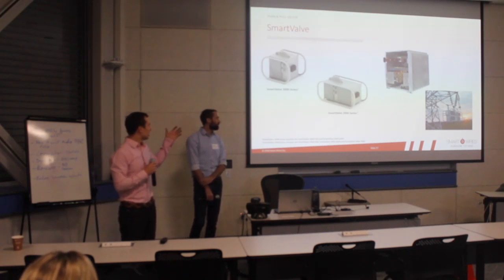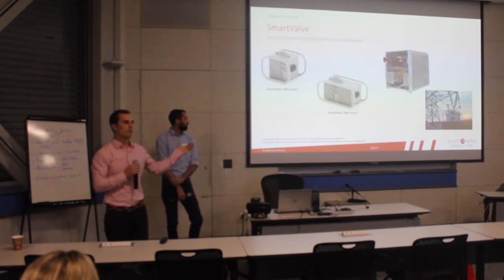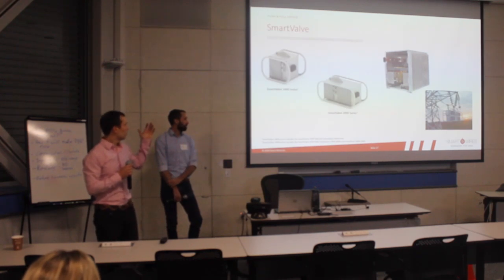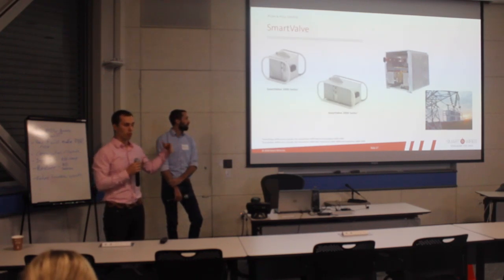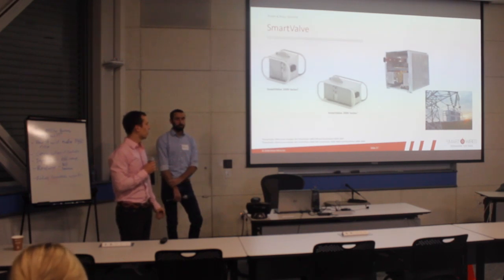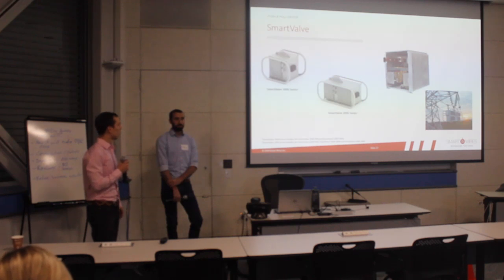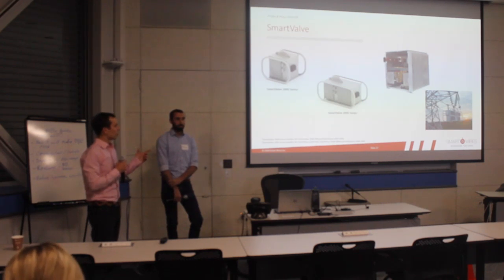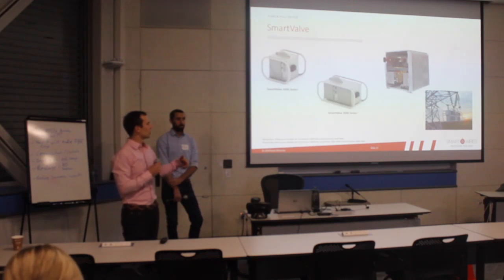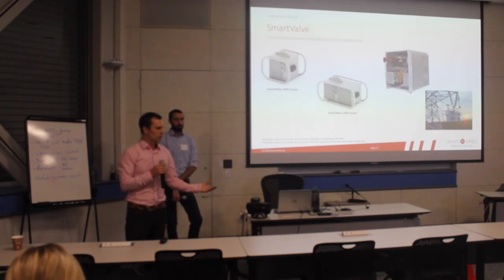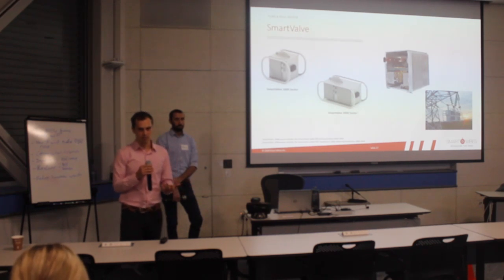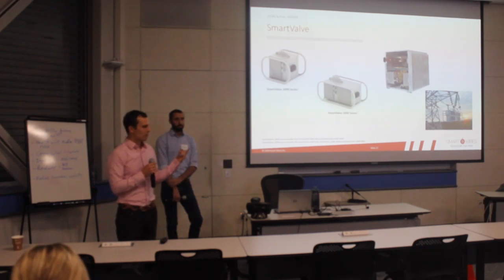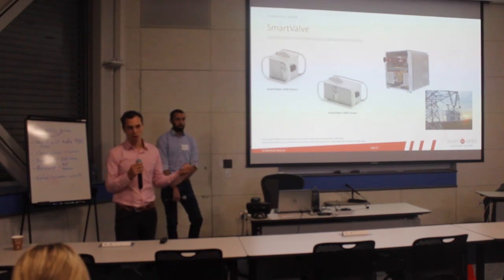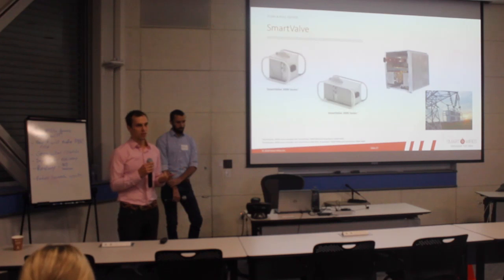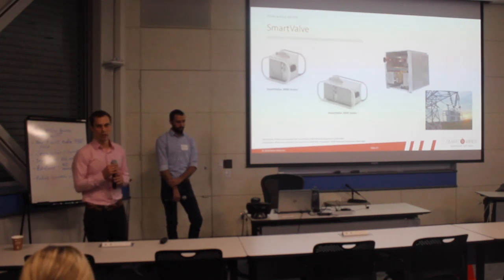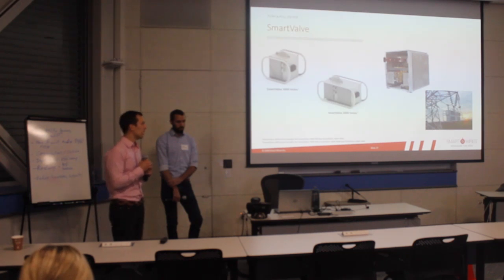We're developing this technology, called the 1000 and 2000, referring to its MVA rating. The Smart Valve 1000 produces 1,000 kilovolt amps, and the Smart Valve 2000 does 2,000 kilovolt amps. That's the equivalent of about 5 Tesla Model S's, to put it in perspective. So in that little box we have essentially the same powertrain as an electric car, about 5 Tesla powertrains worth, and that's what we're deploying on the grid to increase or decrease the impedance on the line.